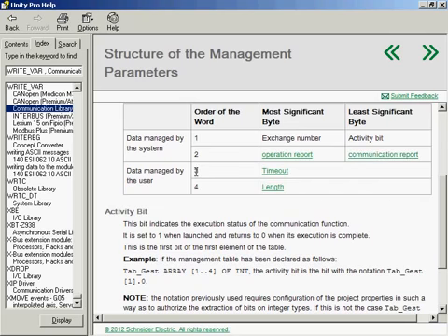The second element of the Exchange Management Table is critical when you're debugging during the commissioning of a project. The communication report is basically a list of the error codes that you can get. So if you're not using the second element of this array, it's difficult to troubleshoot and you won't see any data.